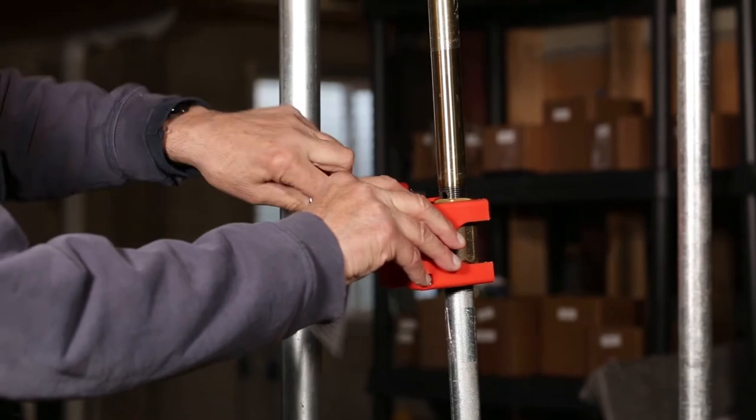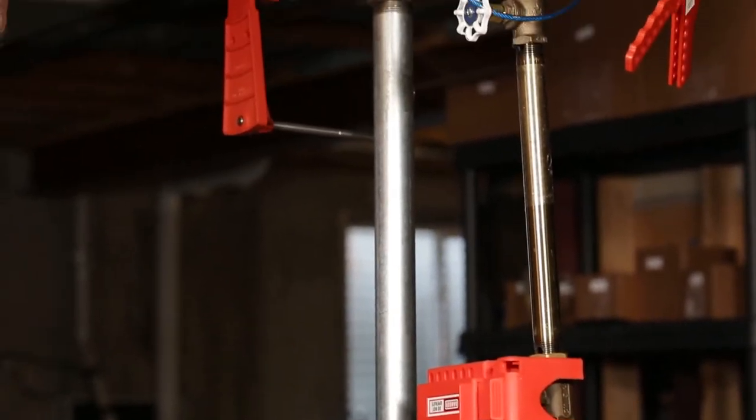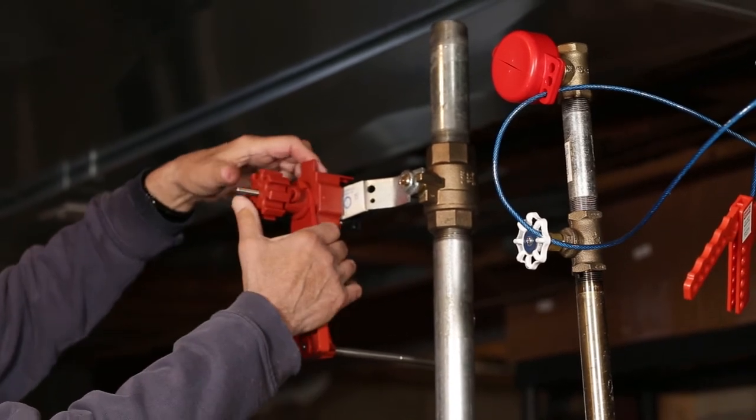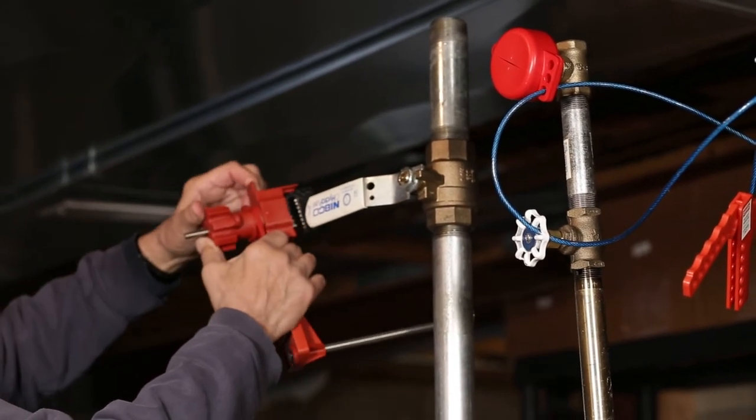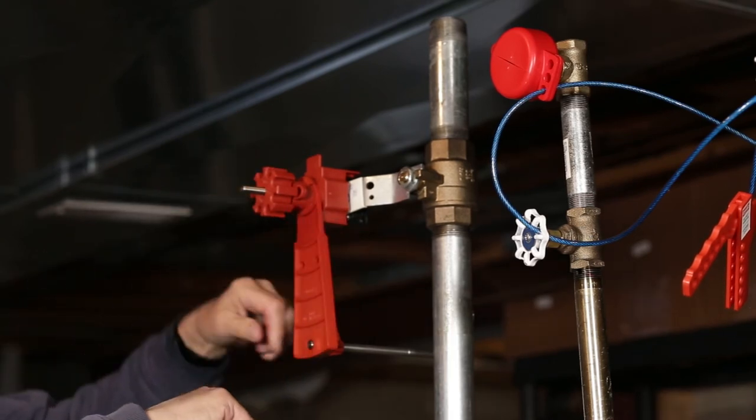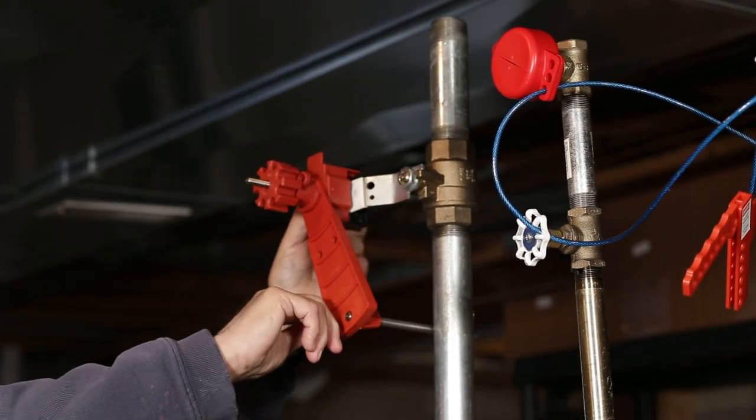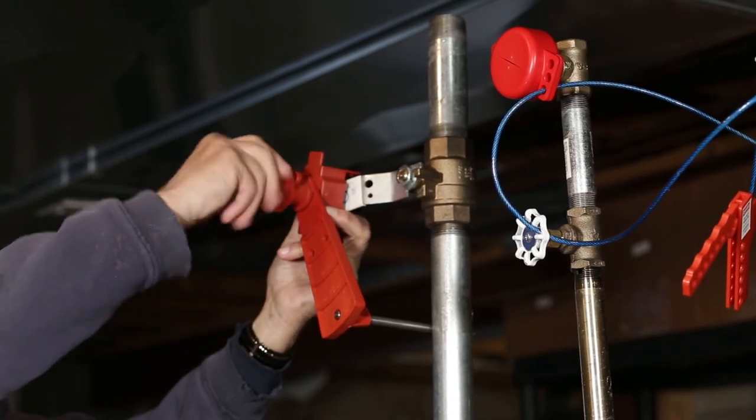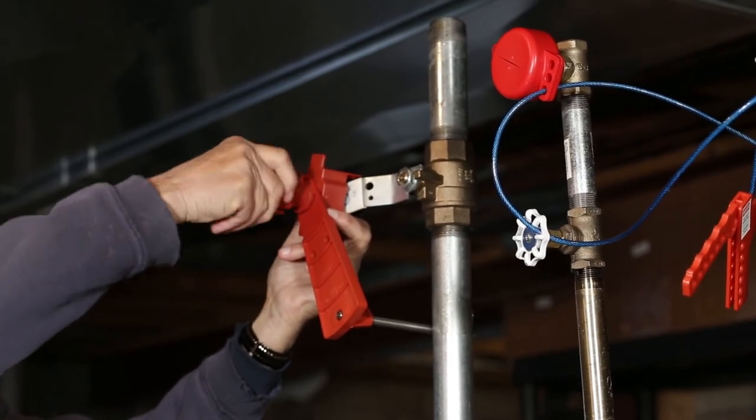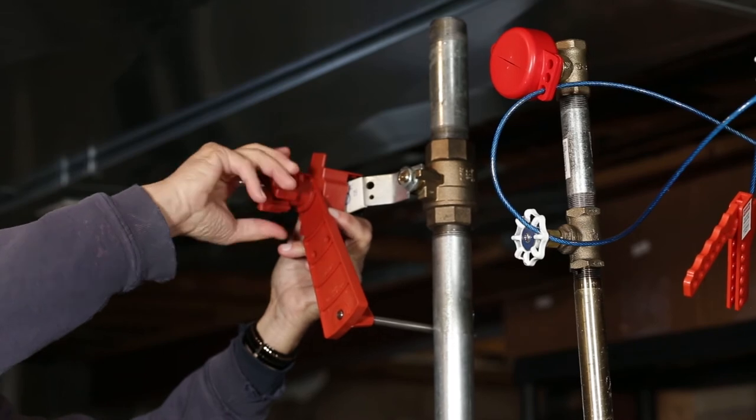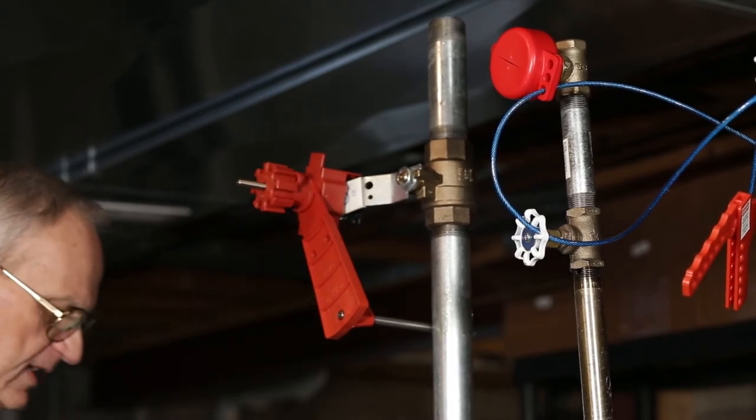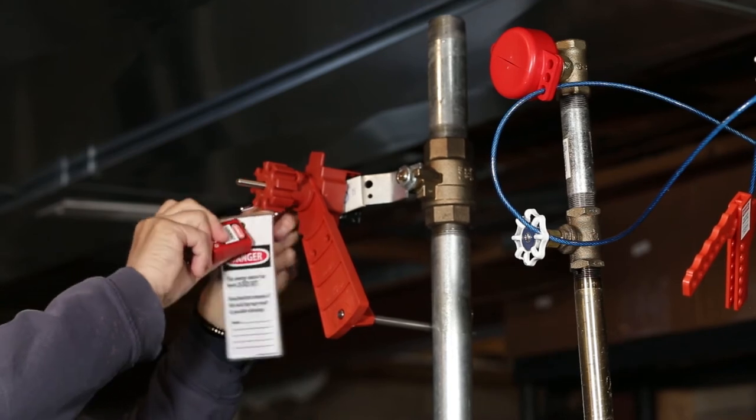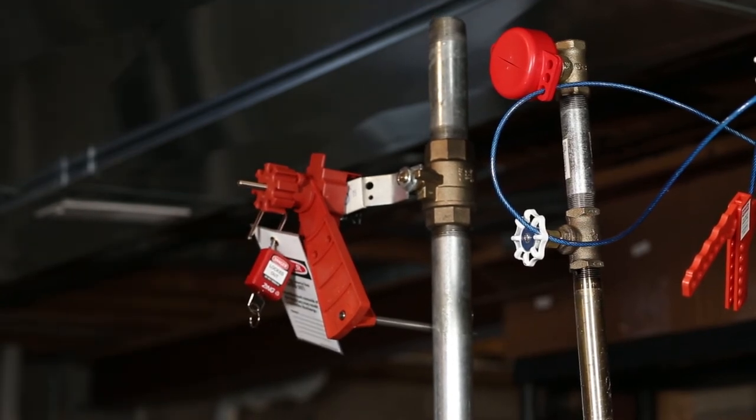The more universal device that's out there now is actually called the universal valve lockout. This is a one-piece device, simply slips on over the handle, release the catch, swing the arm over to the pipe valve body, you tighten the wheel down, and lock and tag will go through the side into the handle, and the device is locked out.